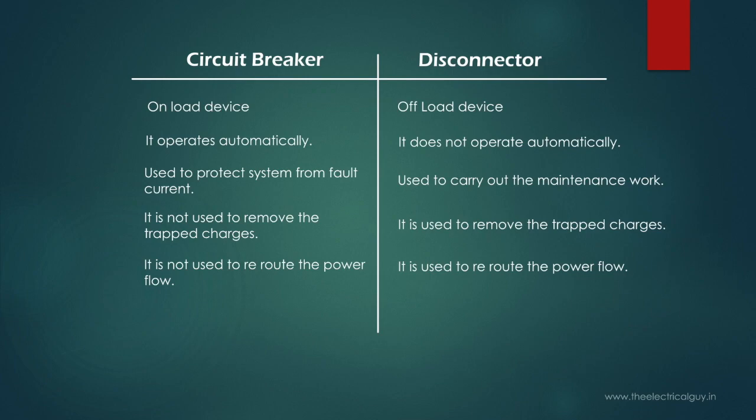While operating disconnector, we must open the disconnector only when the associated circuit breaker is opened. And while closing, we must close the disconnector first and then the circuit breaker.